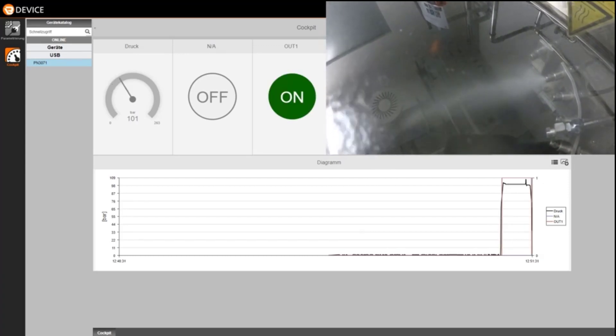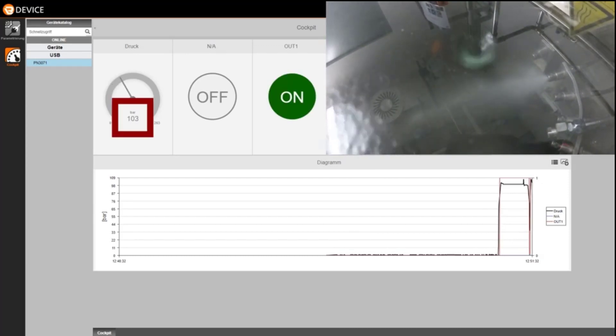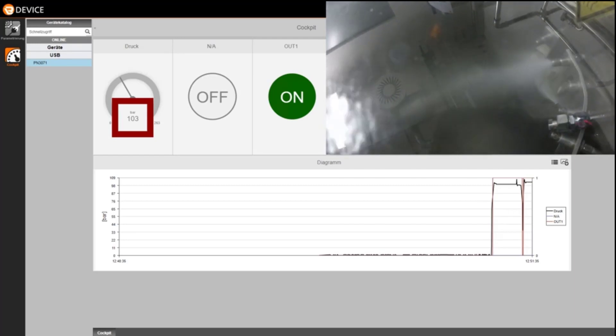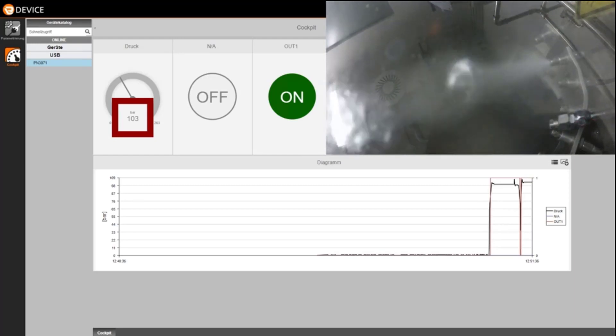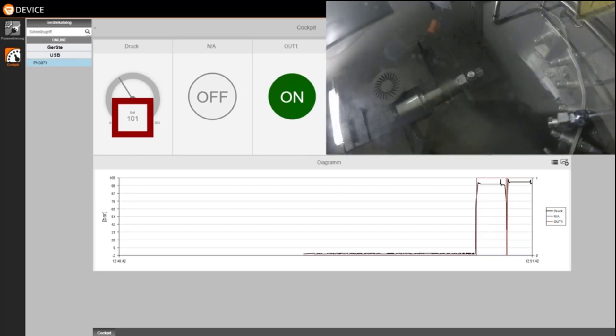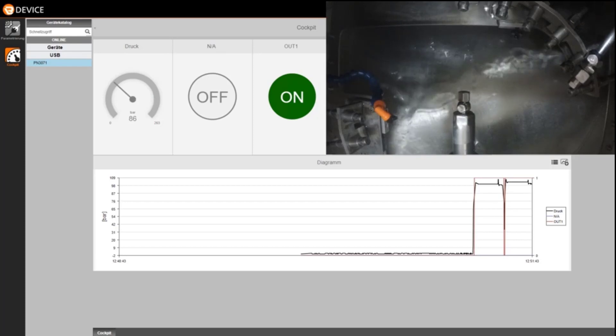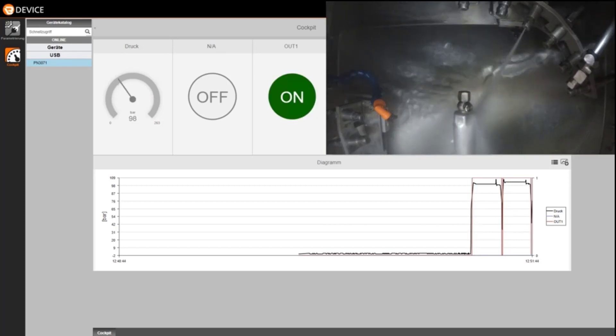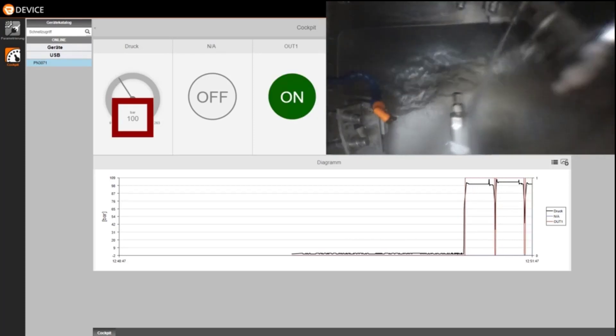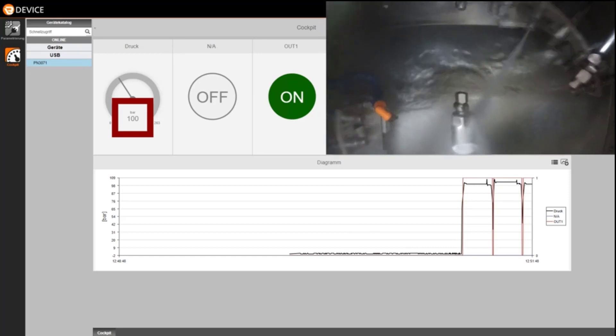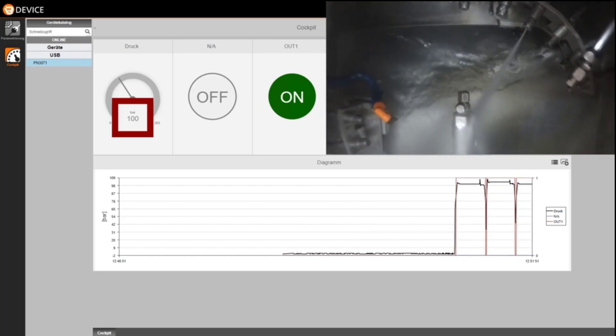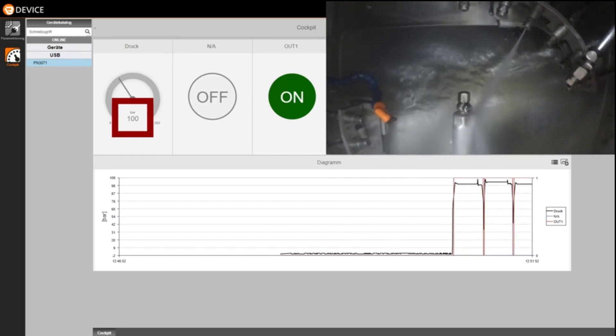But the second nozzle has a process value of only 1 or 3 bar. And the third nozzle has a process value of 100 bar again, which leads us to know that there must be a problem with the second nozzle.